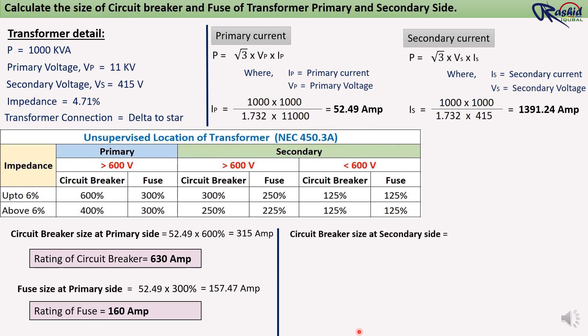Now we calculate the circuit breaker for the secondary side. Secondary current is 1391.24 A. As per the NEC standard, we multiply 125% by the secondary current. This is because, as per NEC rules, if the secondary voltage of the transformer is less than 600 volts, we use a 125% safety factor for both circuit breaker and fuse. In our example, the transformer secondary voltage is 415 volts, so this option applies.